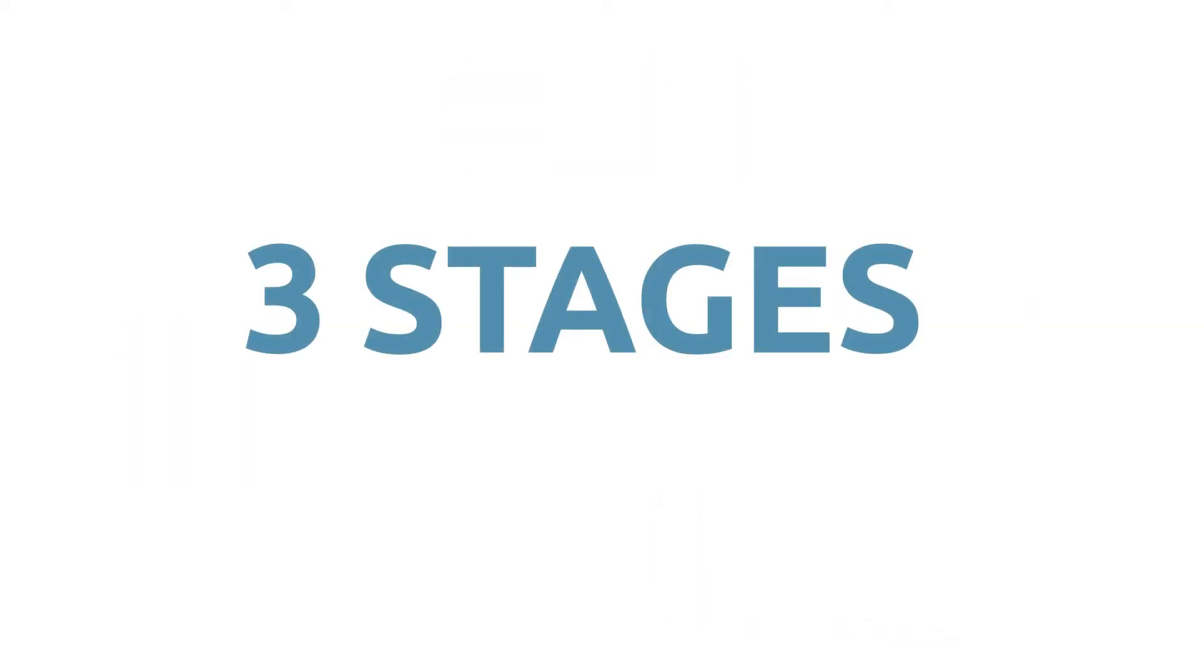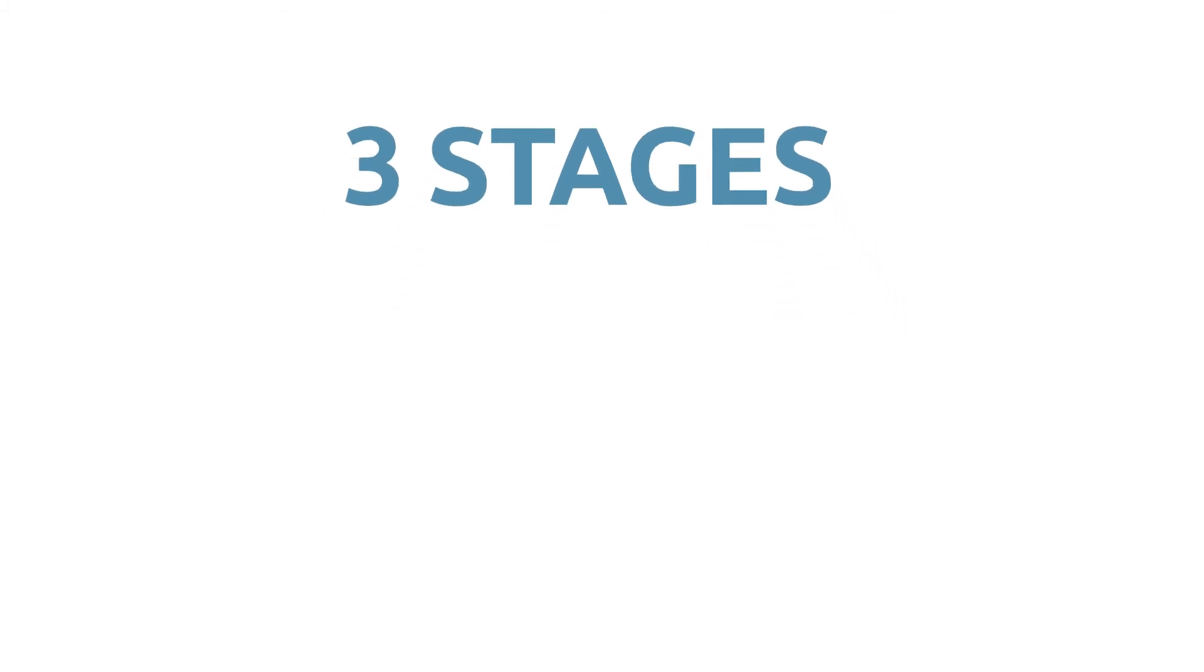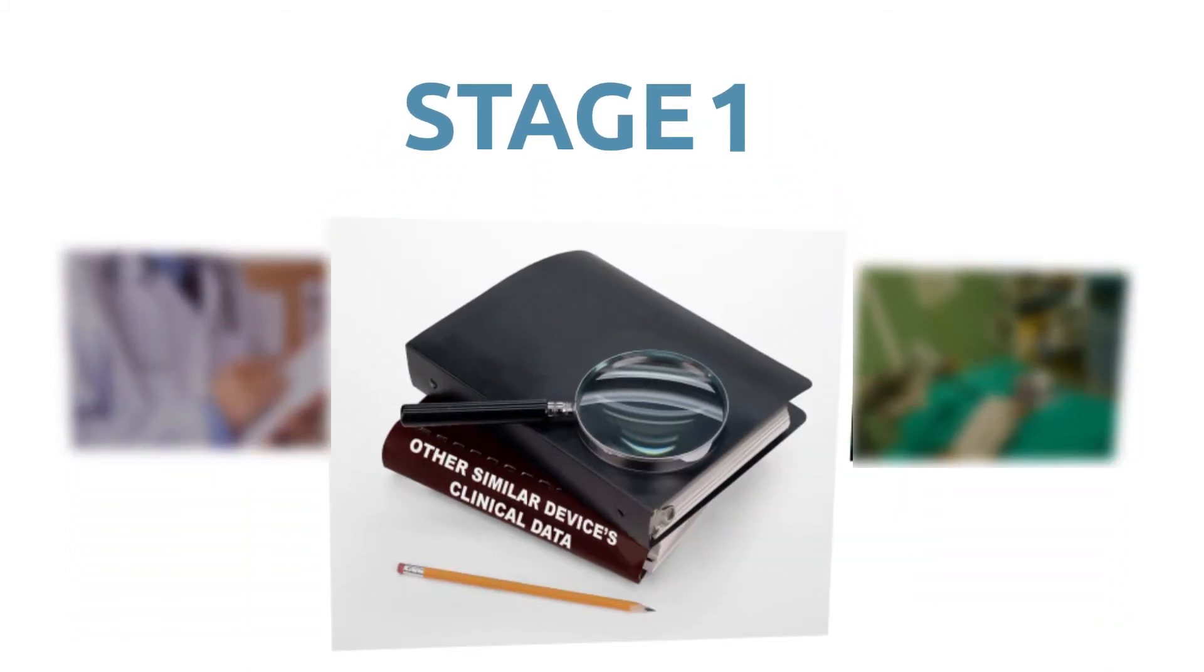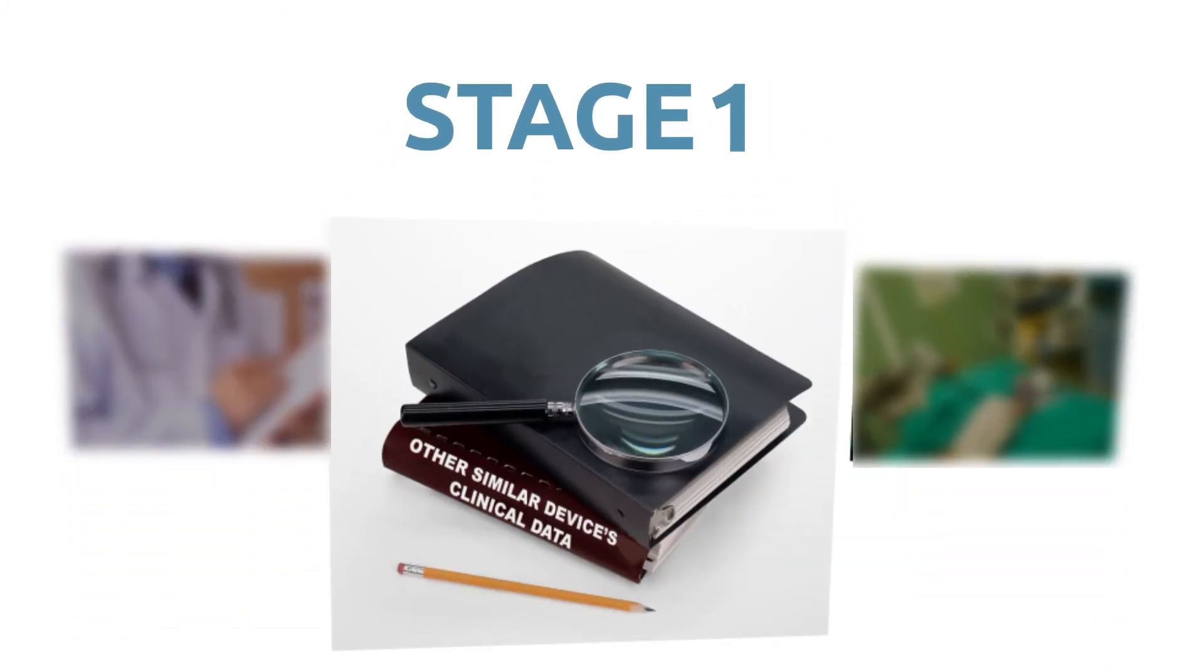A clinical evaluation takes place in three stages. In stage one, manufacturers identify clinical data. This can come from existing literature, clinical experience, clinical trials, or any combination of the three.